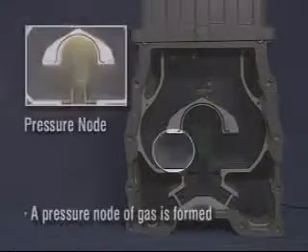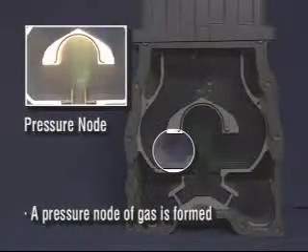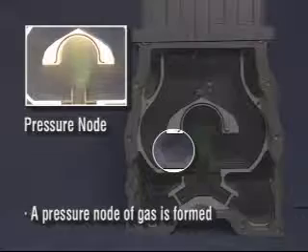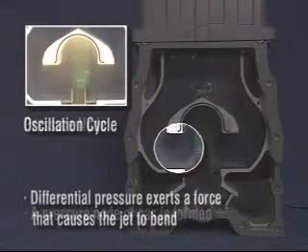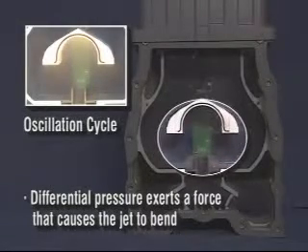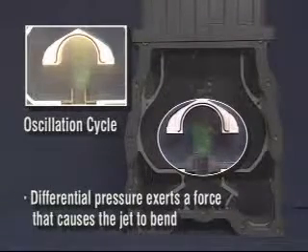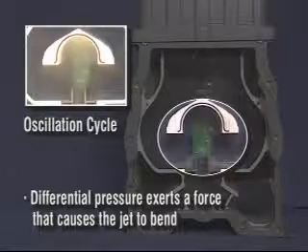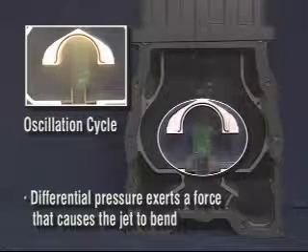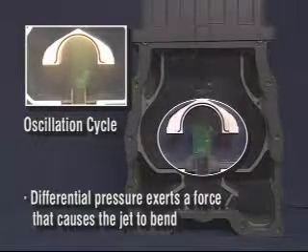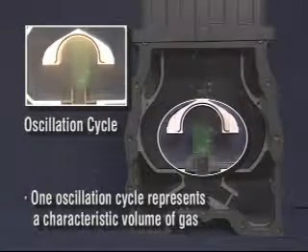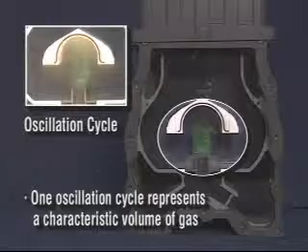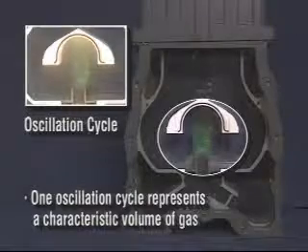A pressure node of gas is formed, creating a difference in pressure either side of the jet. In this way, the jet oscillates from one side of the chamber to the other. One oscillation cycle represents a characteristic volume of gas.